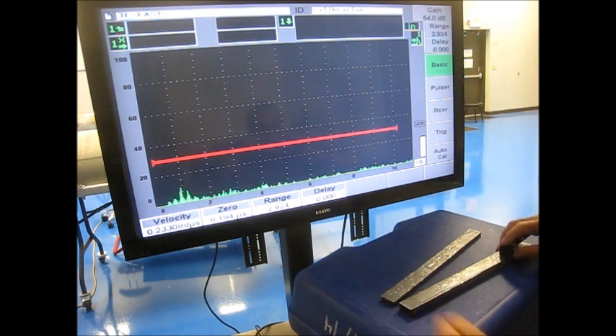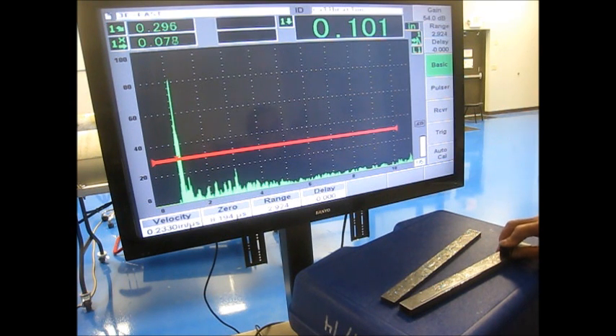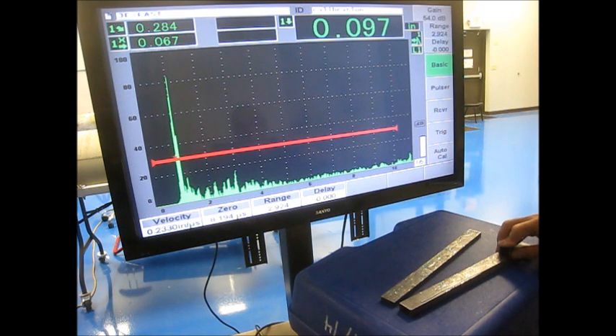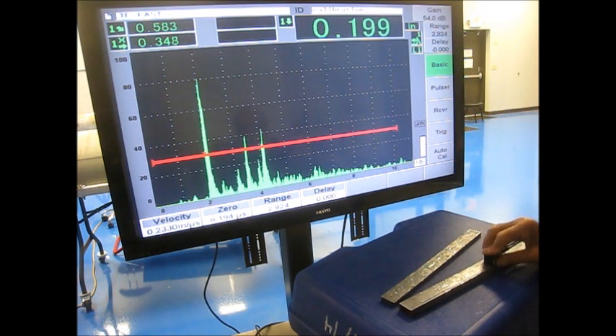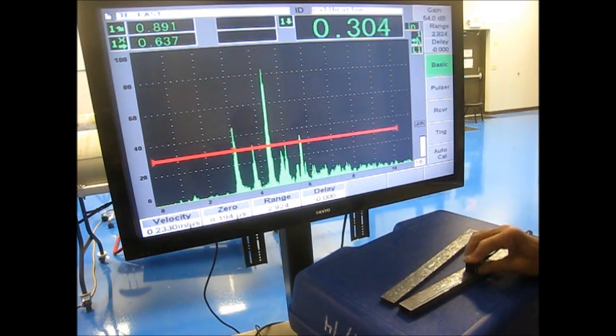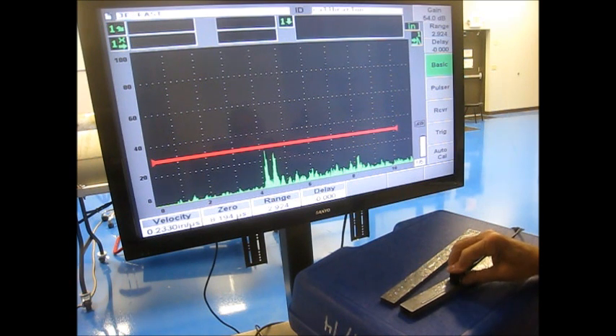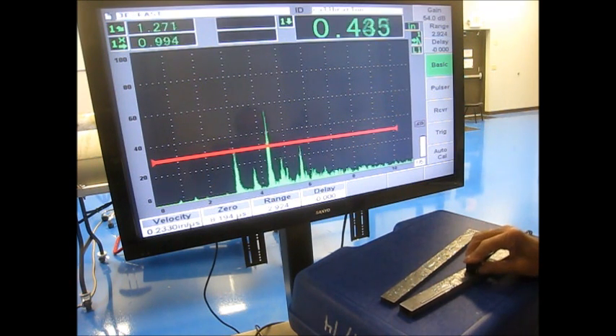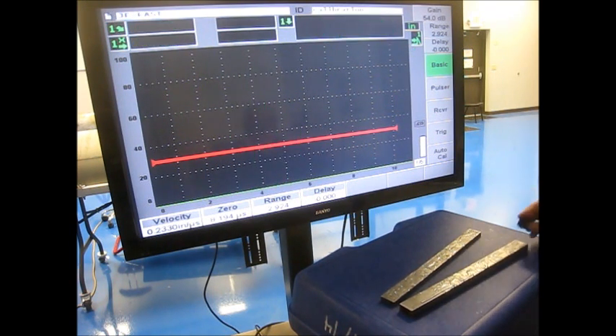I'm going to go to each side drill hole. This is a positioning cal, so I'm just going to put the transducer index point right on the notch mark for the 100 hole. 1 is at 1, 2 is at 2, 3 is at 3, 4 is at 4, and the 300 hole is about 50% screen height.